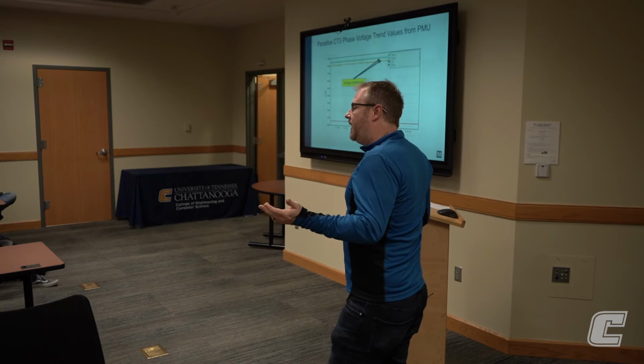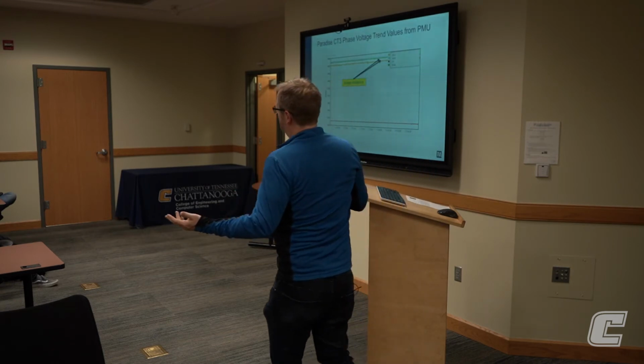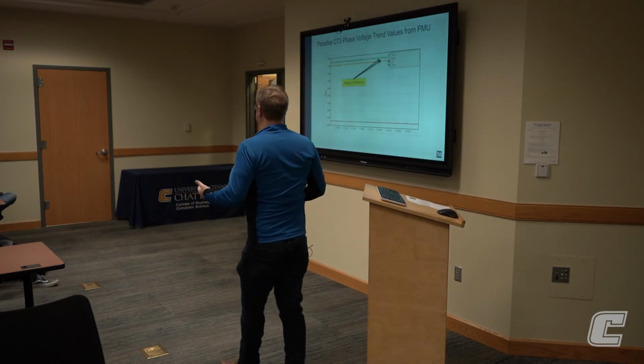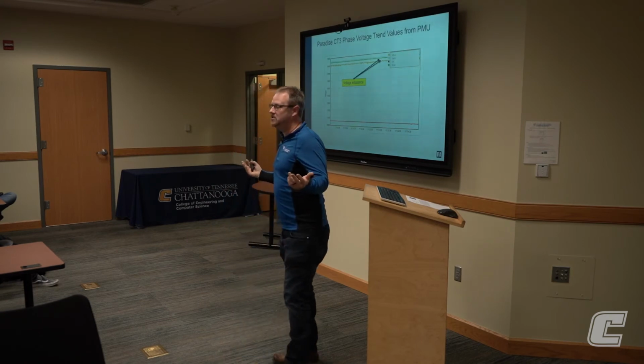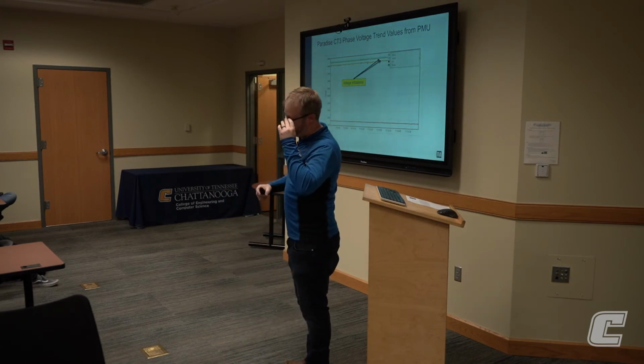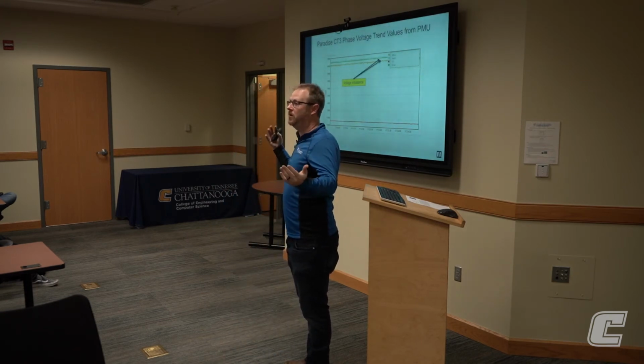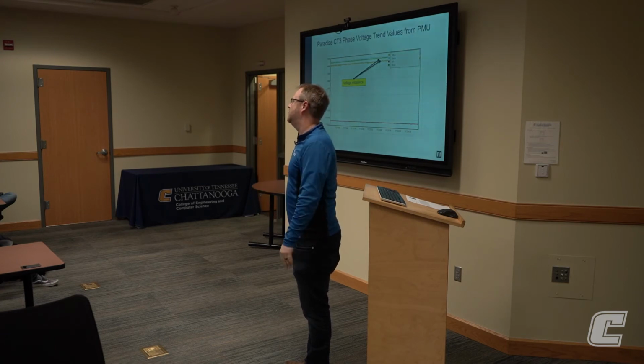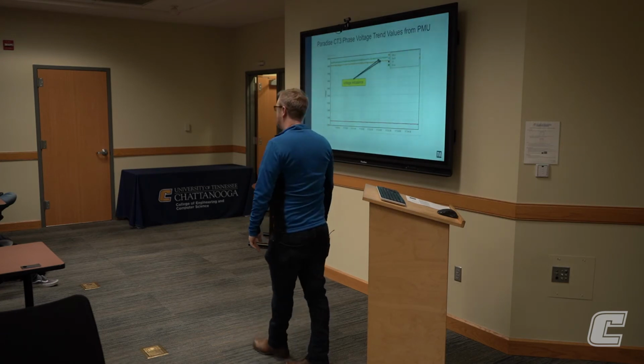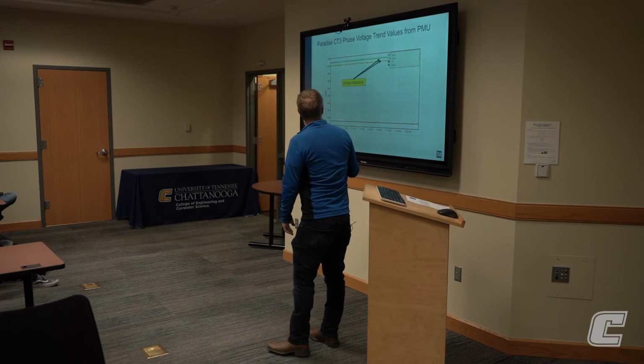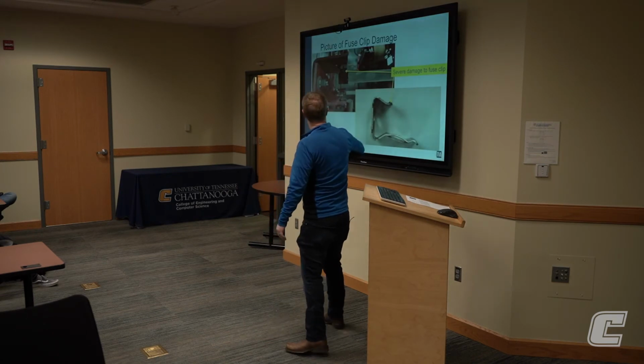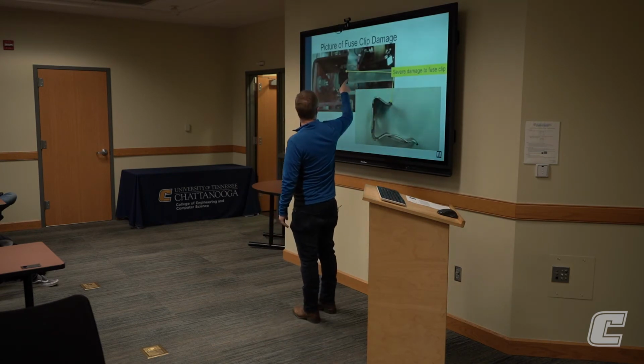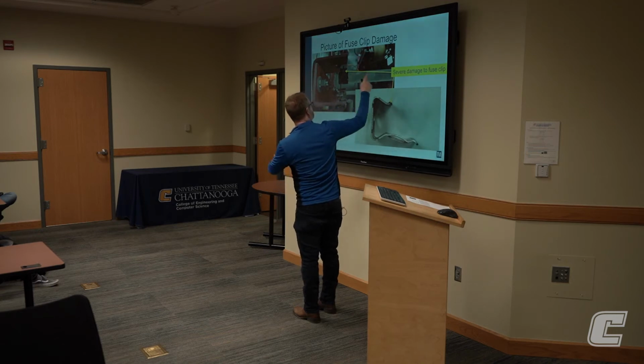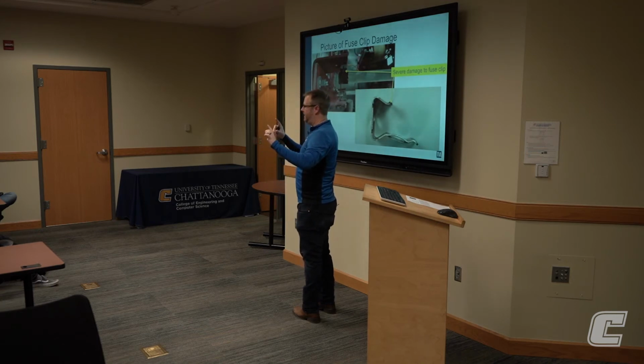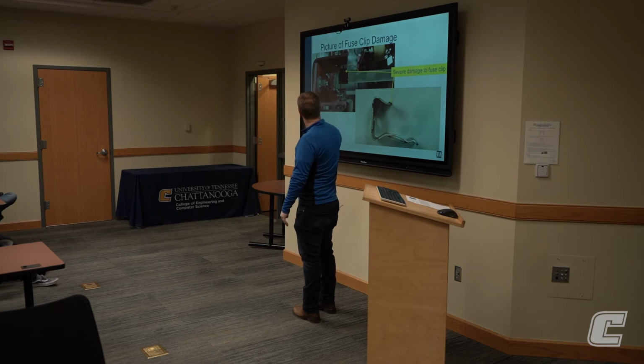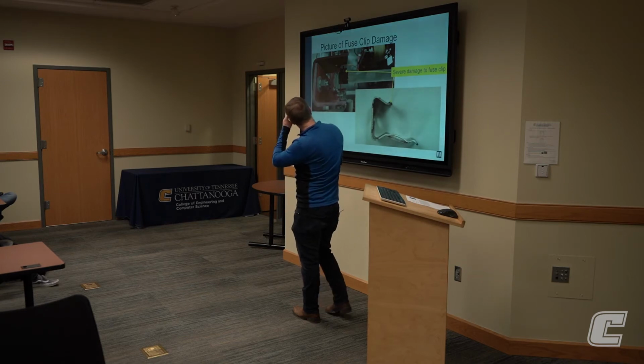So we called the plant and said, you need to look at this. We're getting an alarm. I don't know what's going on. And they said, perfect. We're getting ready to take a plant outage. They do outages quite a bit to do maintenance work during the spring and fall when people aren't running their air conditioners and heaters as much. And so they said, we'll look at it this fall. And they did, and this is what they came back with. This is a fuse. I don't remember what voltage it is, but it's a fuse. It's probably about that big. I think it's maybe a 2,000 or 3,000 amp fuse.